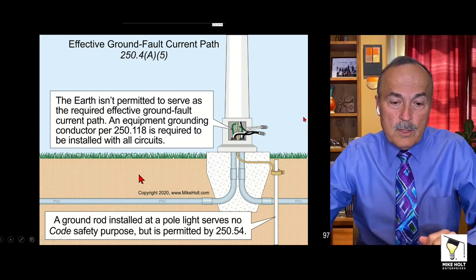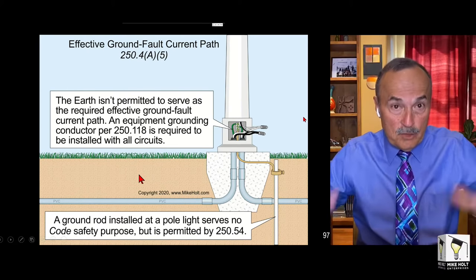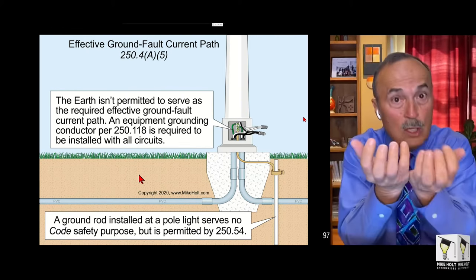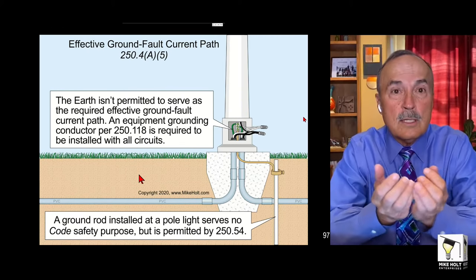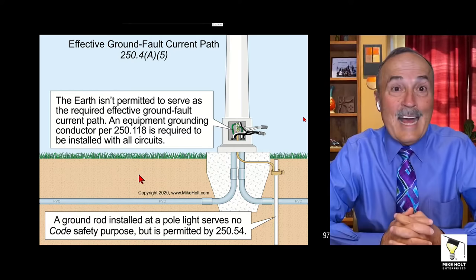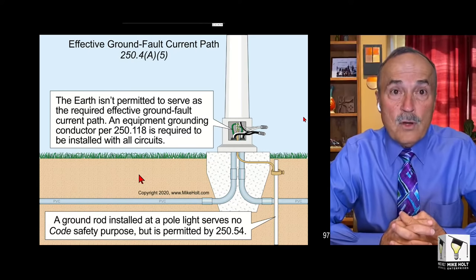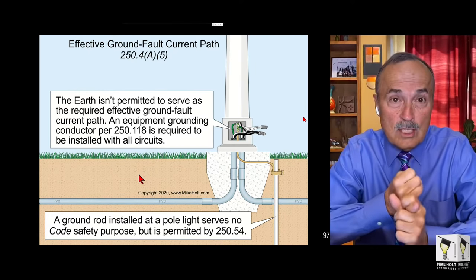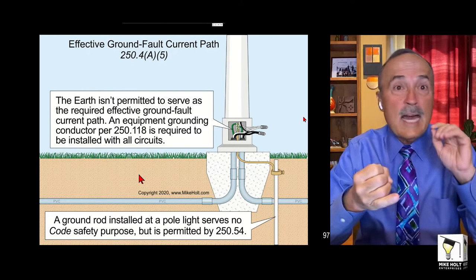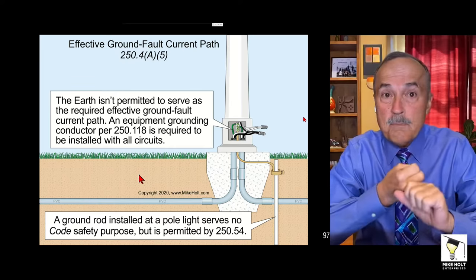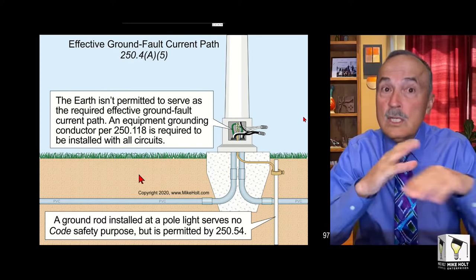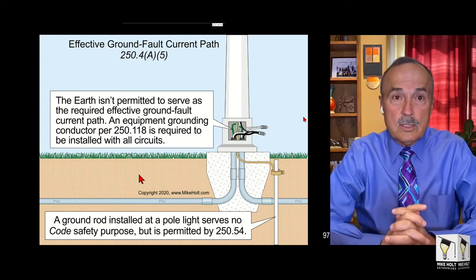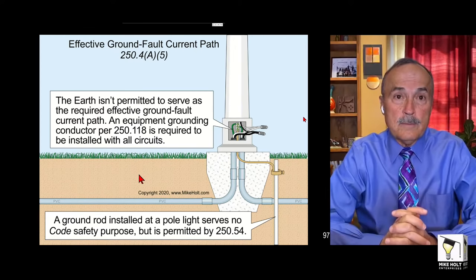Now, the earth - the dirt itself - just dirt. Go outside, pick up some dirt, look at that dirt. That is not an effective ground fault current path. It's not intentionally constructed, and it's not a low impedance path back to the source. So we can never use the dirt to clear a fault.